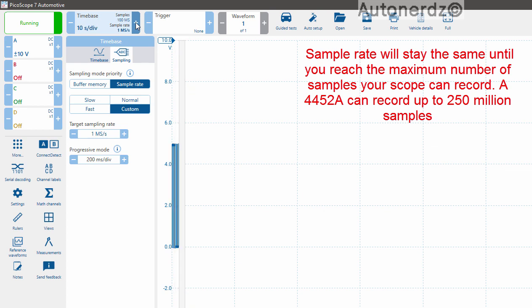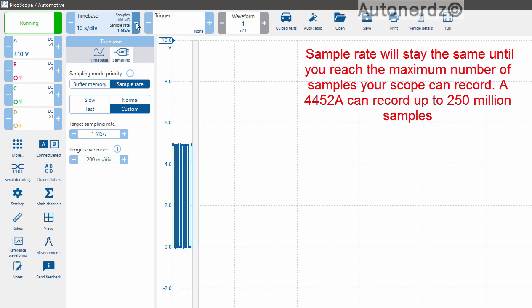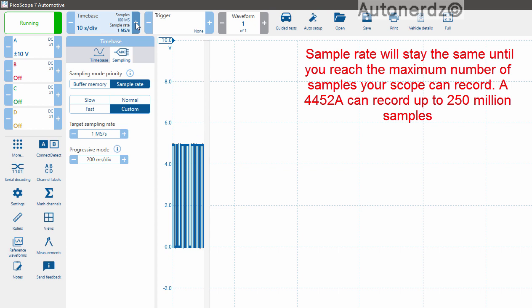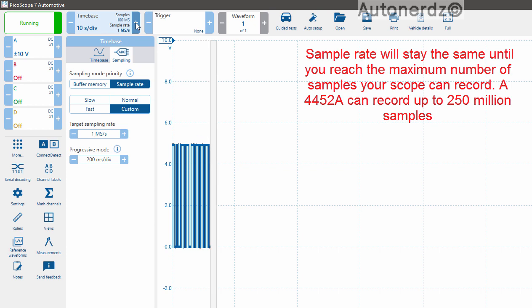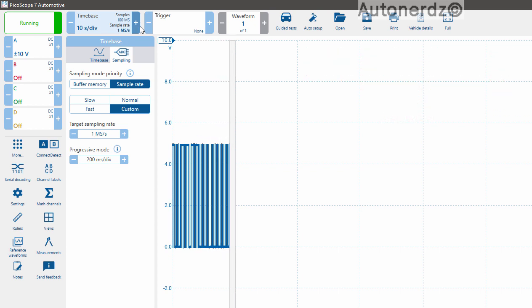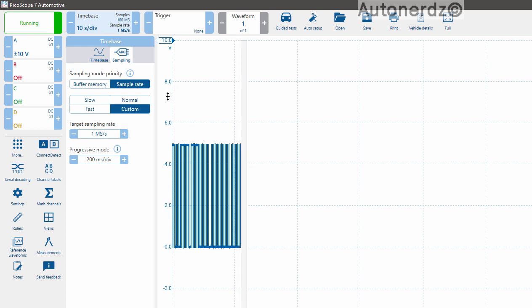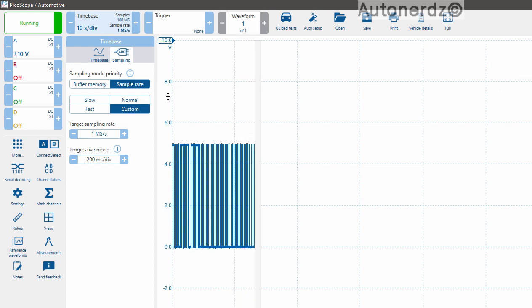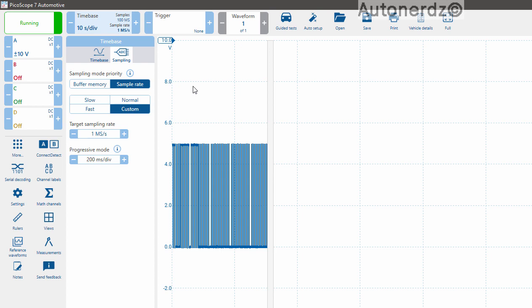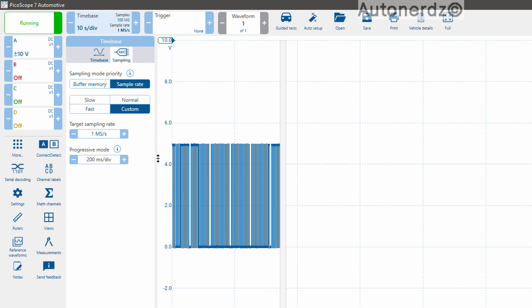Our sample rate up here will stay the same as we increase our time divisions. Which means that we no longer have to worry about matching our sample rate to our time base. We can set it and, I don't want to say forget it, but we can set it and not have to worry about it as much.